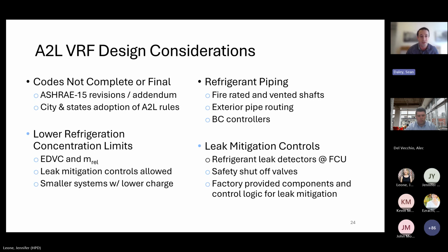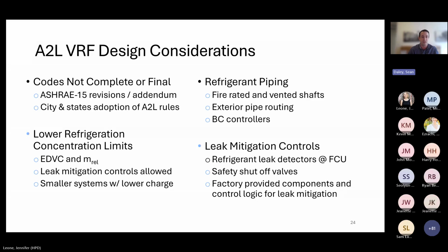So next, I'm just going to go over some design considerations for the A2L refrigerant systems. Things are a little different, as Kevin went over, with the A2L refrigerants. We have to be a little more careful in how we handle these inside the building. The first challenge right now is that codes are not complete or final. ASHRAE 15 just released a new 2024 version within a matter of weeks with some additional changes, and that seems to be a constantly evolving standard. There are still discussions around some addendums and revisions that may need to happen.